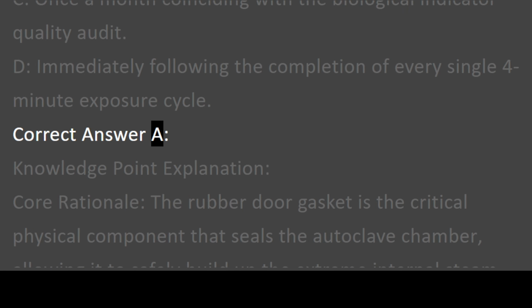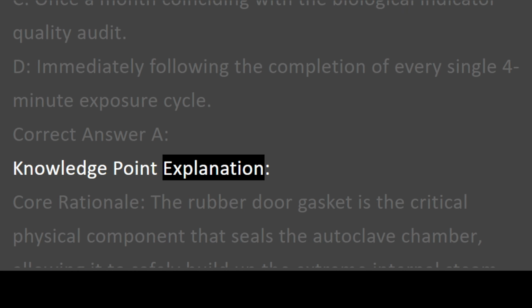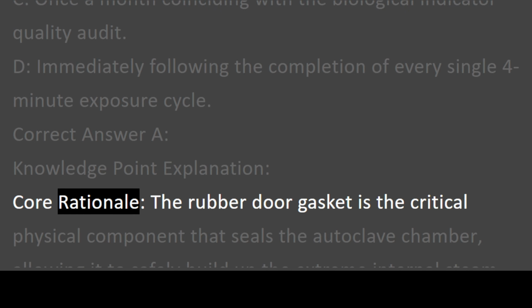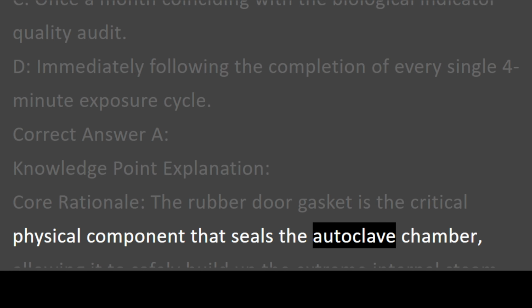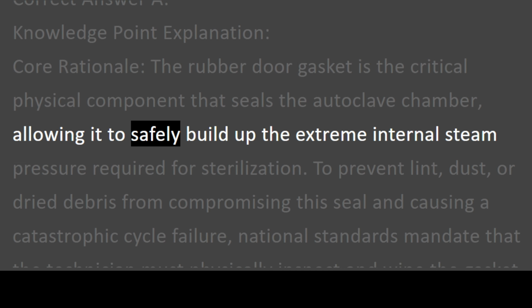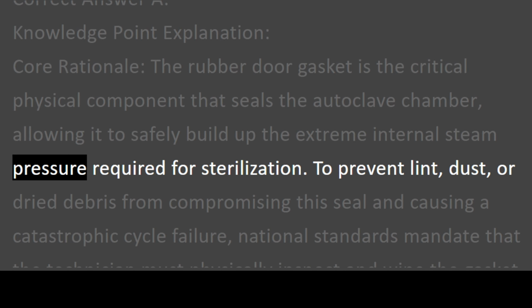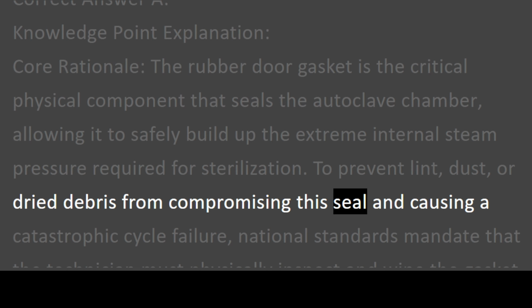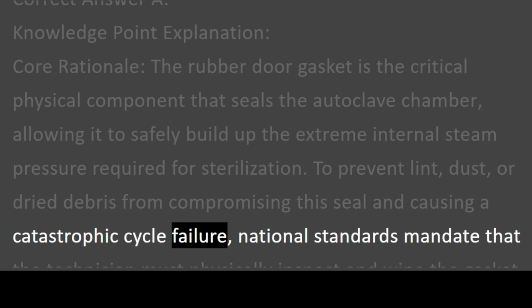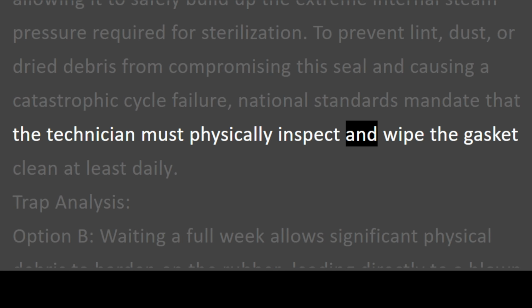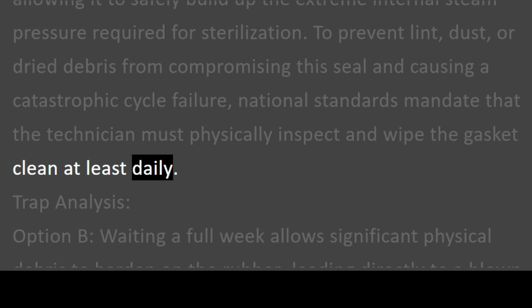Correct answer A. Knowledge point explanation. Core rationale. The rubber door gasket is the critical physical component that seals the autoclave chamber, allowing it to safely build up the extreme internal steam pressure required for sterilization. To prevent lint, dust, or dried debris from compromising this seal and causing a catastrophic cycle failure, national standards mandate that the technician must physically inspect and wipe the gasket clean at least daily.